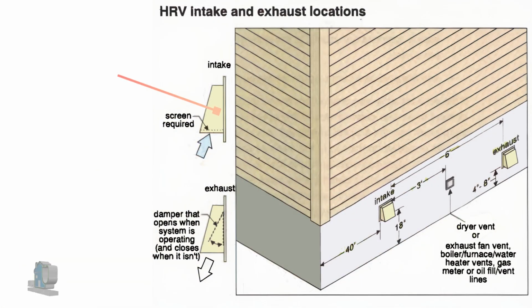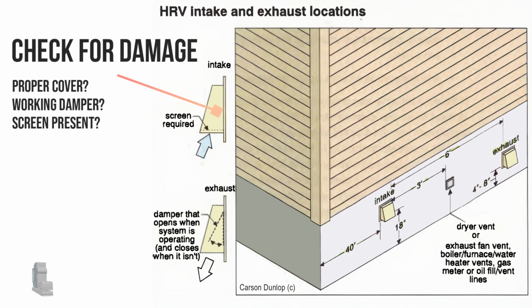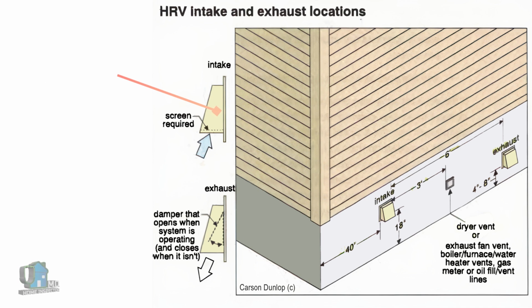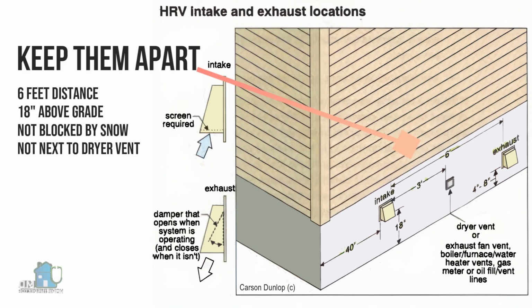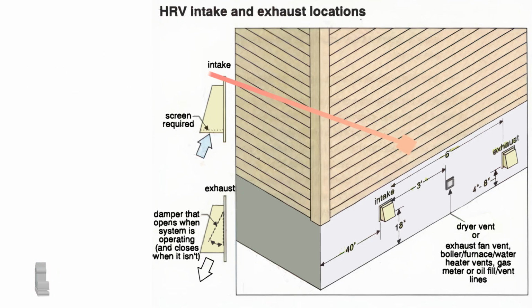If you find that you do have an HRV in your house, make sure the outdoor terminations for the exhaust and the air intake are properly done. The air intake should have a screen to prevent anything other than air from entering. The exhaust should have a functional damper that opens and closes easily. The intake and the exhaust should not be next to each other and be around 6 feet away. You also want to see the intake at least 18 inches above grade so it is not blocked by snow. You also do not want something like a dryer vent near the intake because you don't want lint to be brought back into the house.